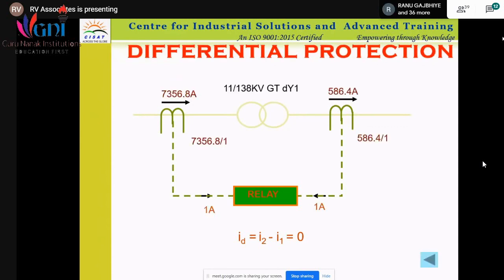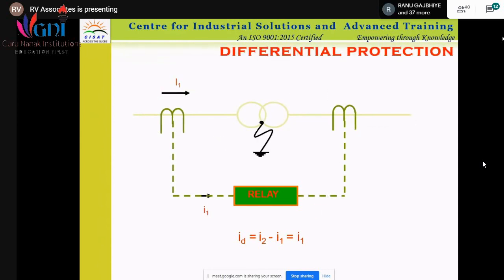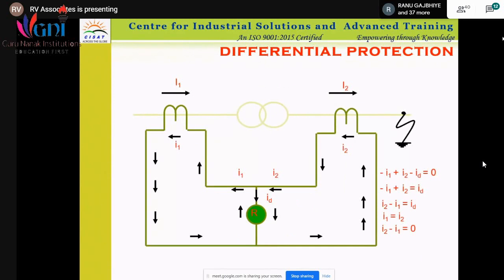Whenever there is a difference in the windings because of a fault, this is what differential protection is. Just see the diagram. Whenever there is a difference between two windings, current will flow through the relay, which has been identified, and it will trip. This is how differential protection works. The same connection is used for the motor.